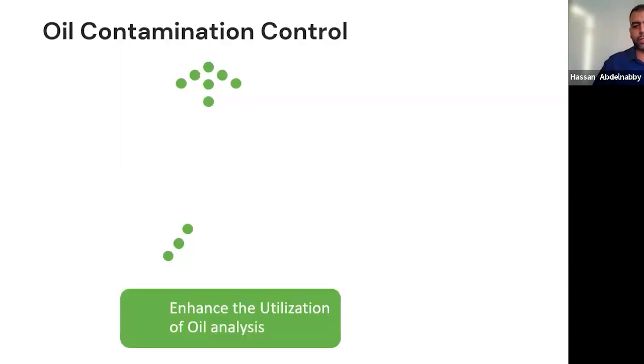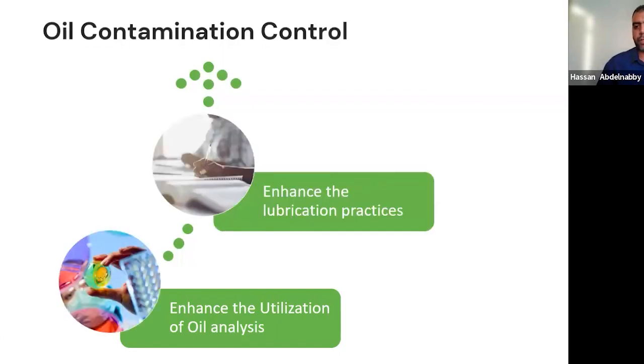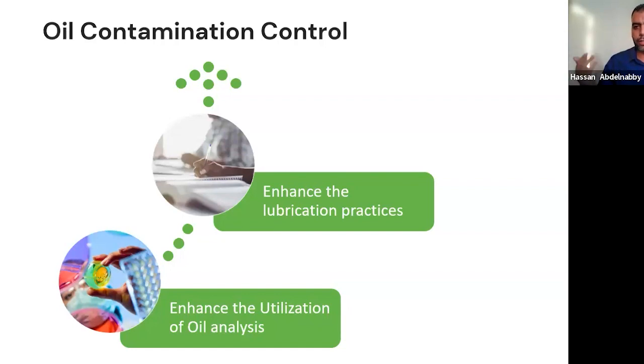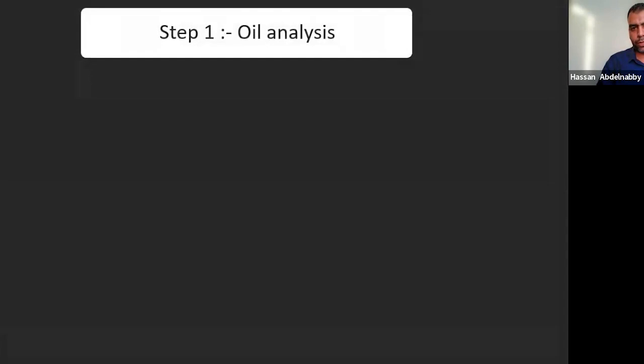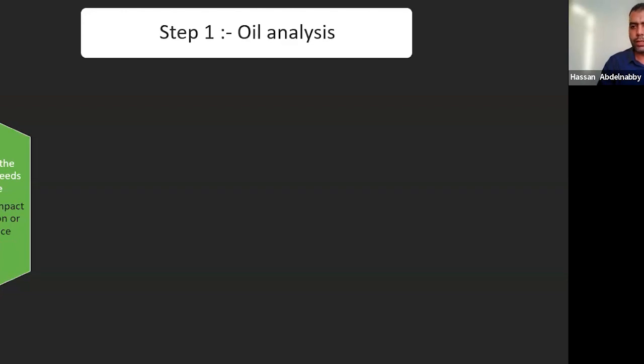Oil contamination control is a journey that starts with enhancing oil analysis utilization while simultaneously enhancing lubrication practices. If you enter a factory and don't know where to start, work on both edges — see what you are attacking and attack it properly. The first stage is oil analysis: you need to know where you are. Determine the assets you need to care about, assess their criticality, and decide whether to include or exclude them at the start of your program.